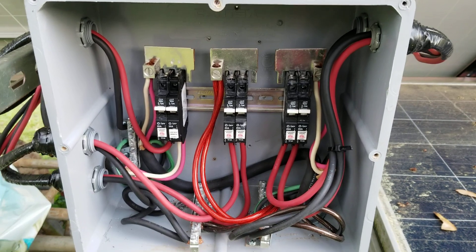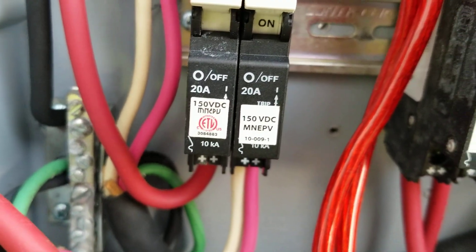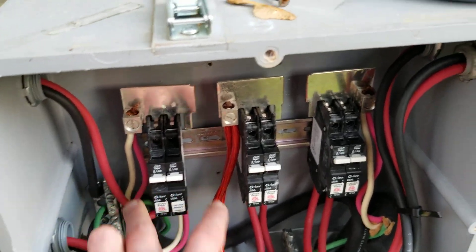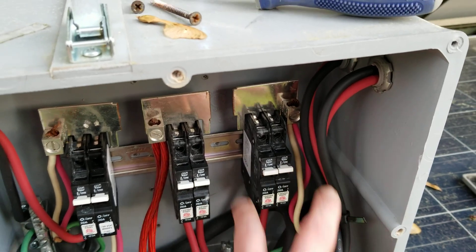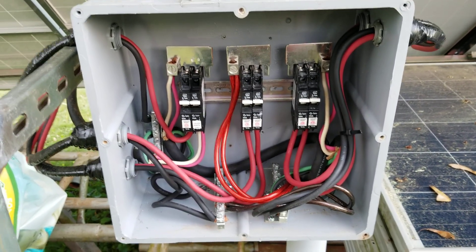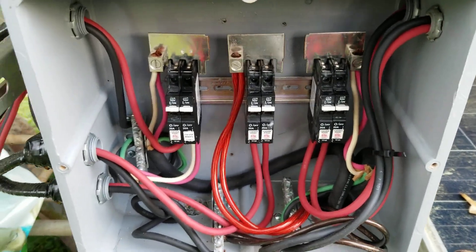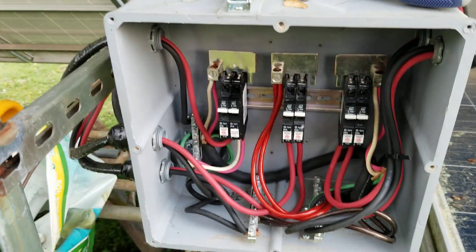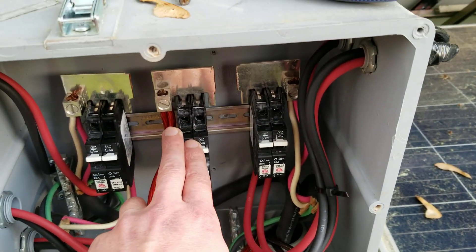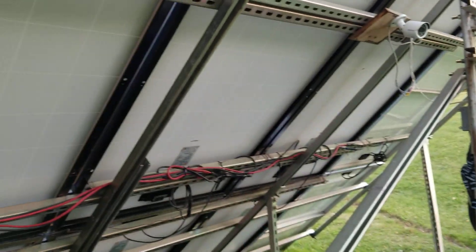This is what it actually looks like inside the combiner panel. I use MidNite breaker switches — they're rated for 20 amp apiece, 150 volt DC. Every two of them controls a certain set of panels. Like, two of these will handle the six large panels I have, and then these two sets here will handle a set of the smaller panels back here in a rack.